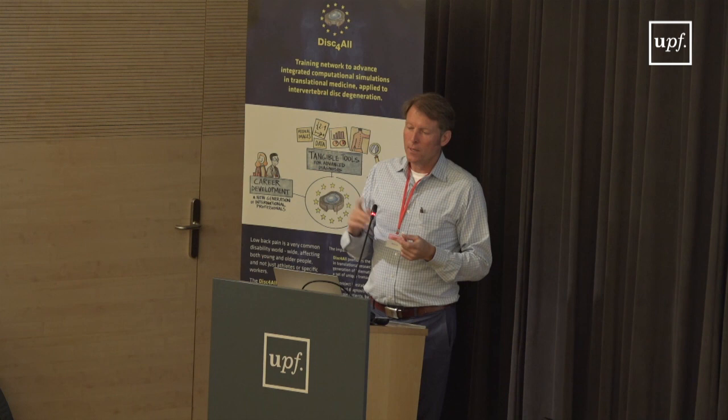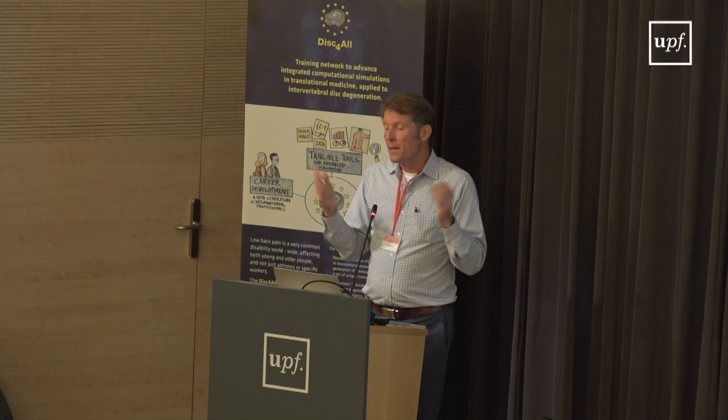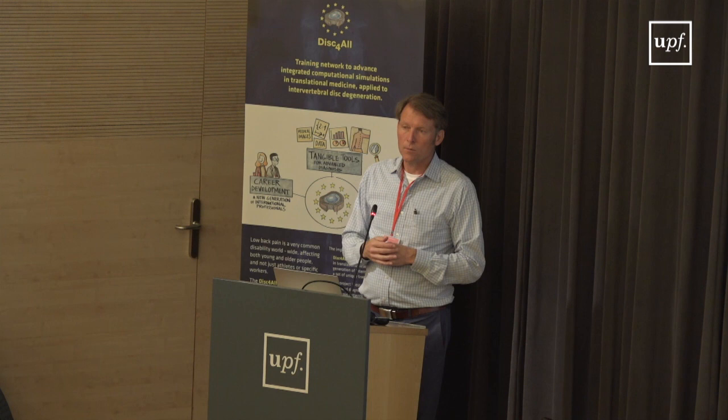Now, when it comes to commercial code versus in-house code, the same rules apply. If you write your own in-house code and it's a low-risk scenario, maybe you don't have to do code verification. But as that risk increases, you're going to be required to do the code verification according to the VV standard. So it really comes down to the risk associated with that model, and then your comfort level in terms of the code that you've used.